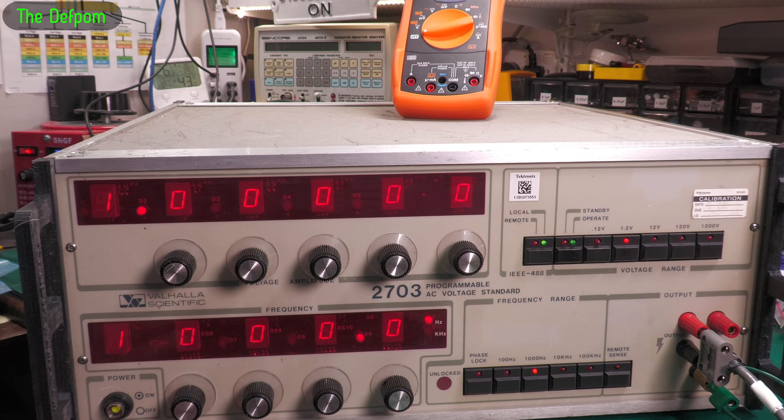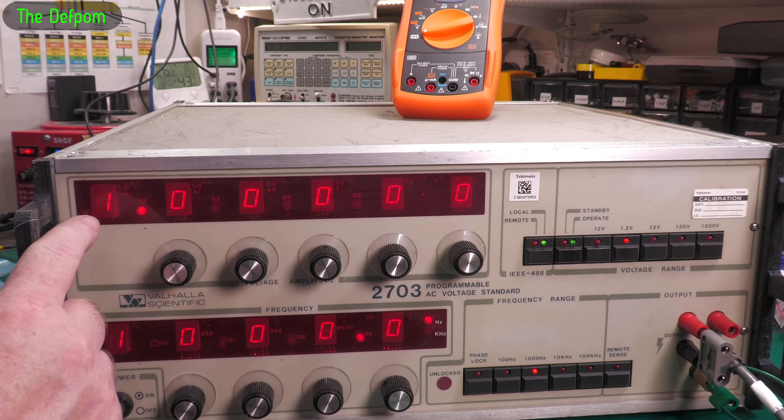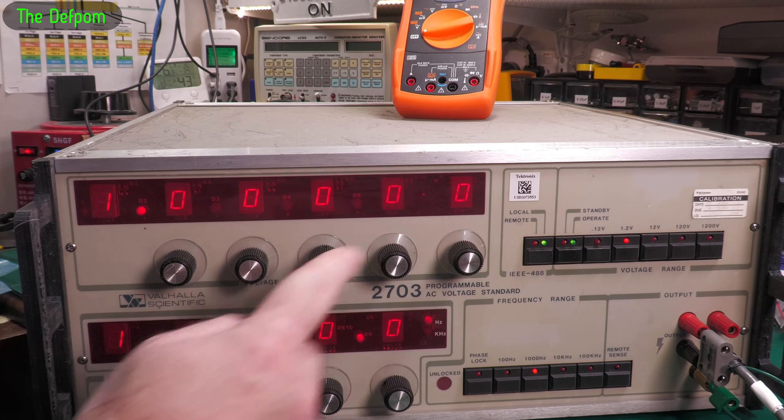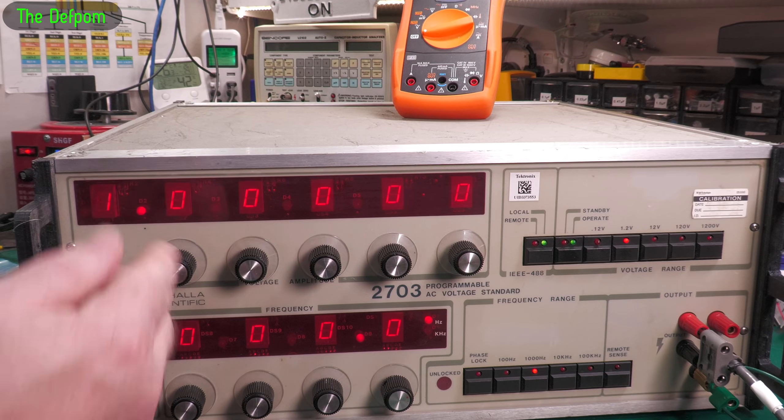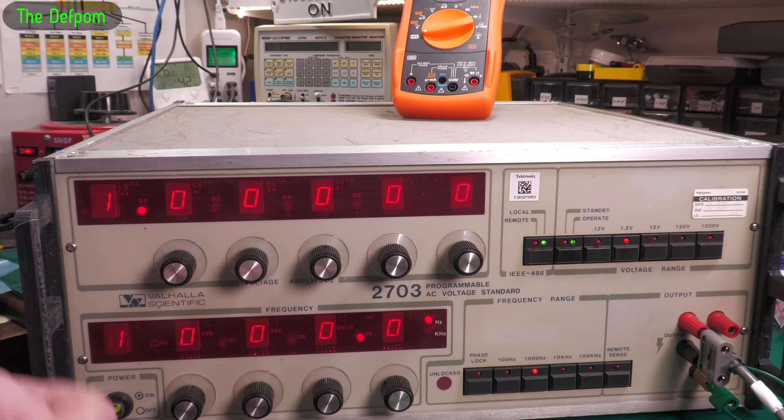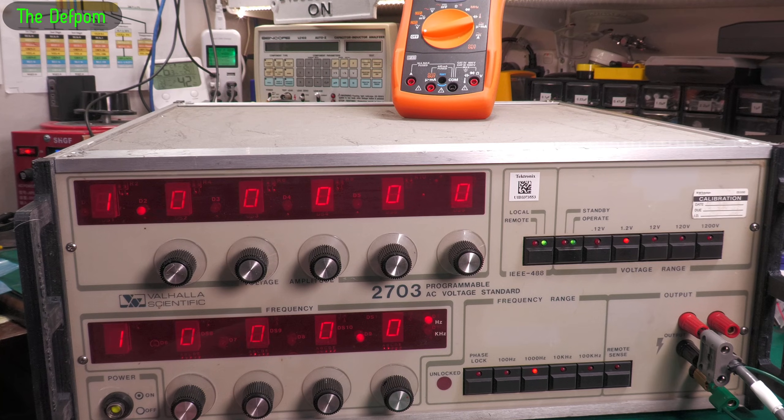The calibration manual only mentions setting up the actual value here, there's nothing about zeroing. There are some trimmers inside for doing zeroing, but they're not for doing big offsets like this. They're just for fine-tuning, so it definitely isn't them.